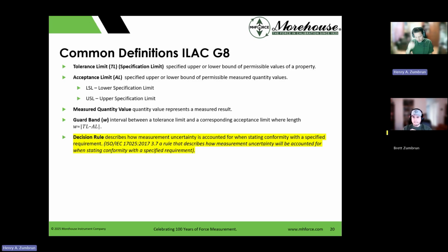Indicated value of reading. There's some people bracket depending on the capacity, but typically the manufacturer is going to say, hey, this is good to 0.1% of full scale. So you say, great. And someone's going to send you a PO that says calibrate to manufacturer spec. And you say, okay, fine.